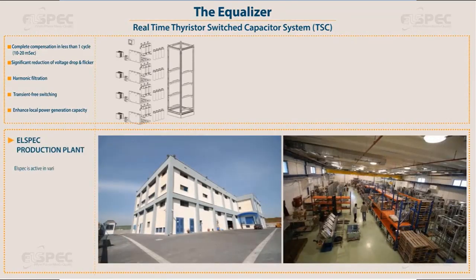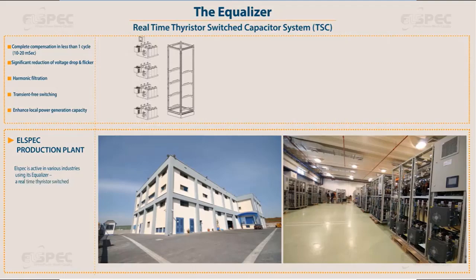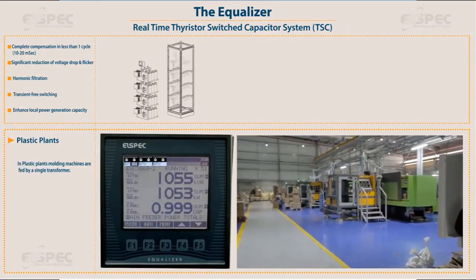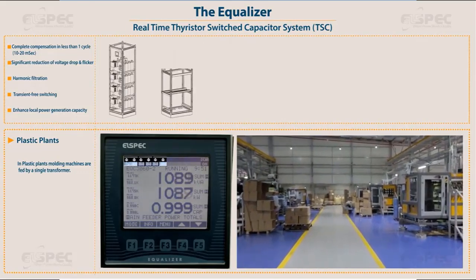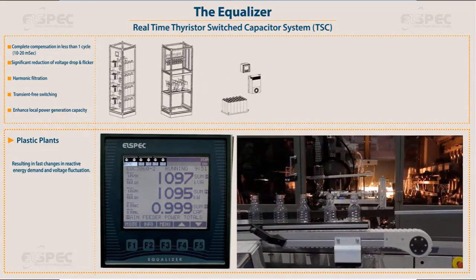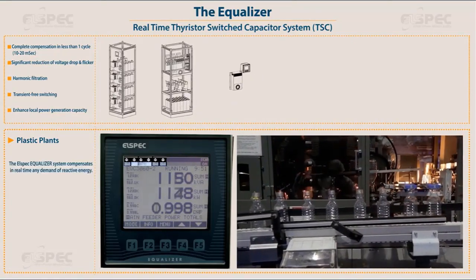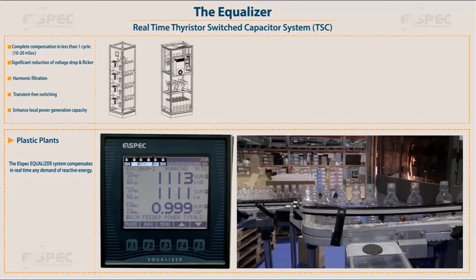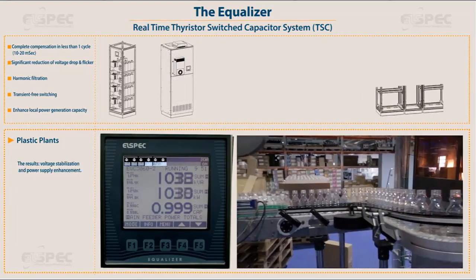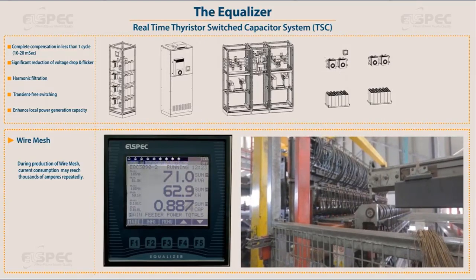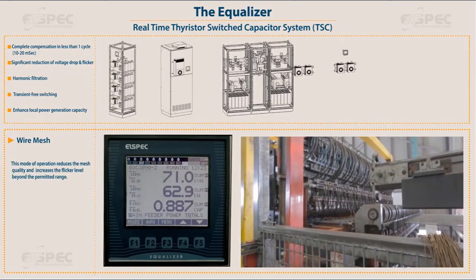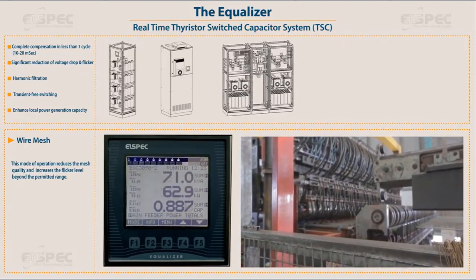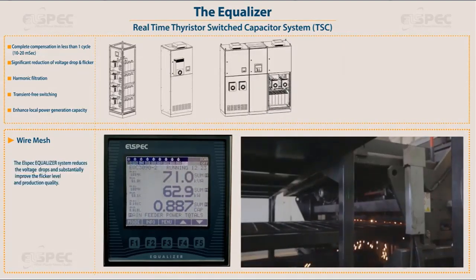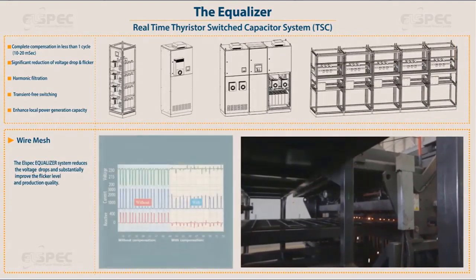ELSPEC is active in various industries using its equalizer, a real-time thyristor switched capacitor system. In plastic plants, molding machines are fed by a single transformer, resulting in fast changes in reactive energy demand and voltage fluctuation. The ELSPEC equalizer system compensates in real time any demand of reactive energy. The results? Voltage stabilization and power supply enhancement. During production of wire mesh, current consumption may reach thousands of amperes repeatedly. This mode of operation reduces the mesh quality and increases the flicker level beyond the permitted range. The ELSPEC equalizer system reduces the voltage drops and substantially improves the flicker level and production quality.